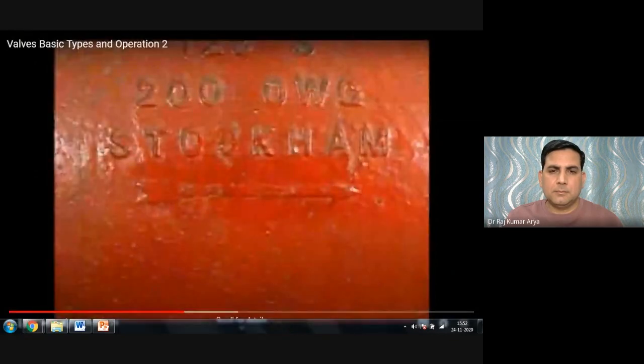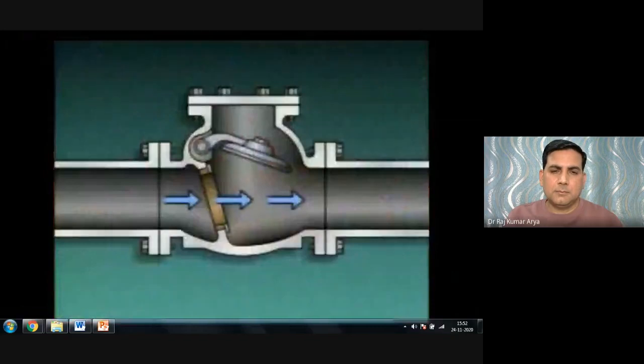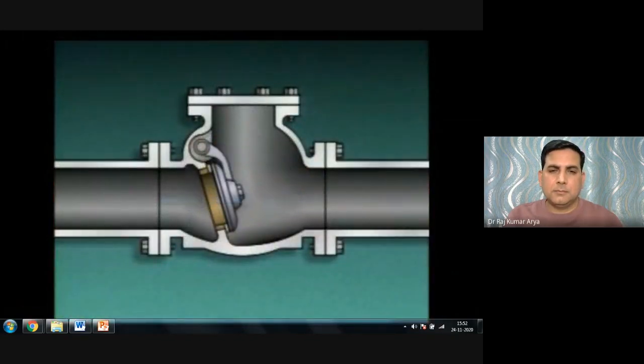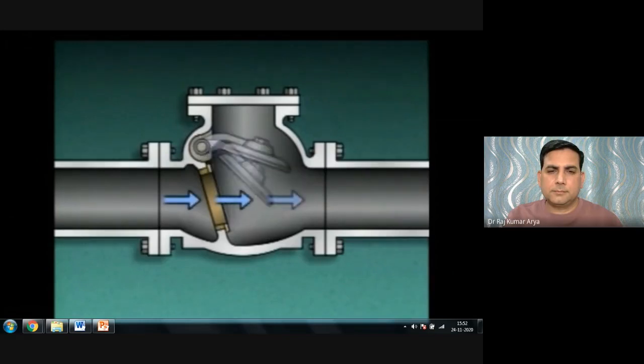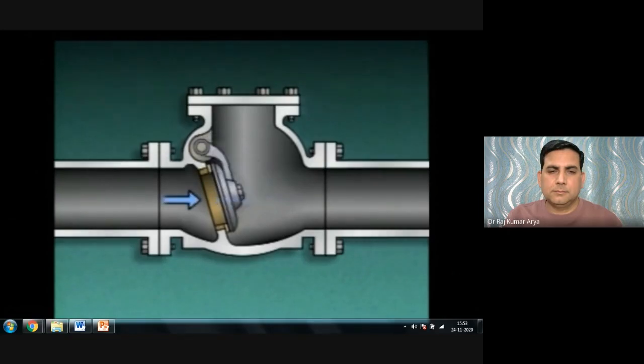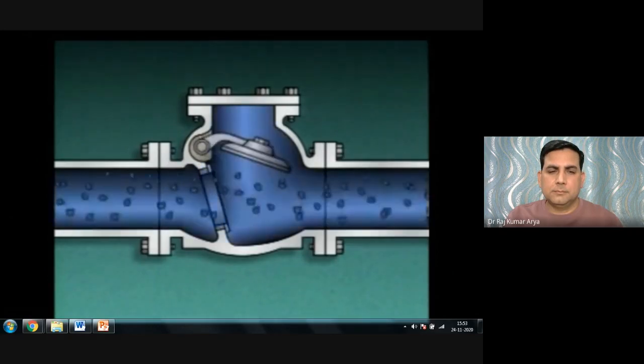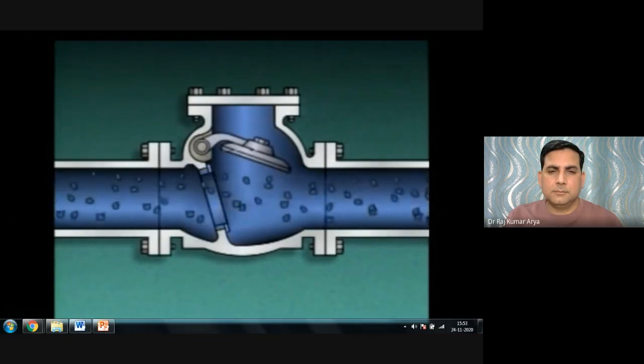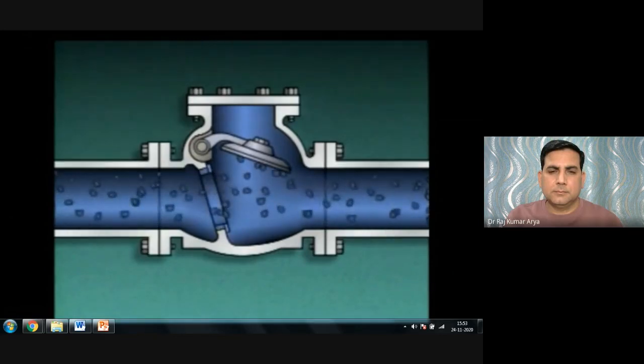As long as flow is constant, the disc remains raised. If flow is intermittent, the disc may repeatedly rise and fall, slamming against the seat. This action can damage the disc and seat, resulting in leakage. This condition can often be detected because the slamming produces noise and vibration in the piping. If you detect this kind of problem, report it to your supervisor. Swing check valves also aren't effective for fluids containing solid particles, as solids can accumulate between the disc and seat and prevent closure.